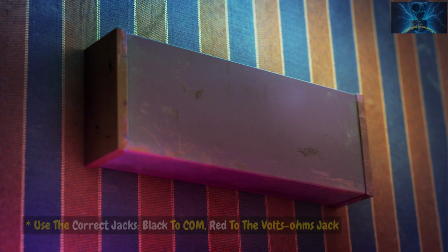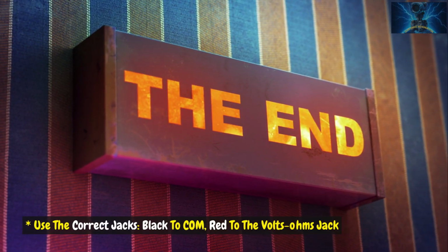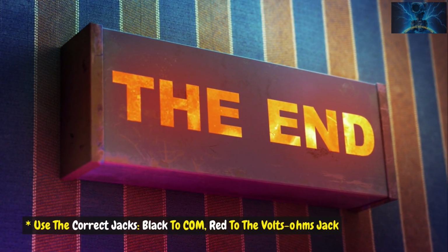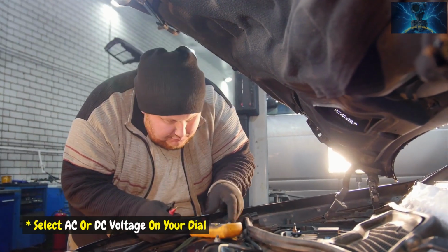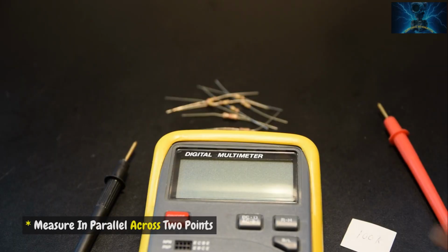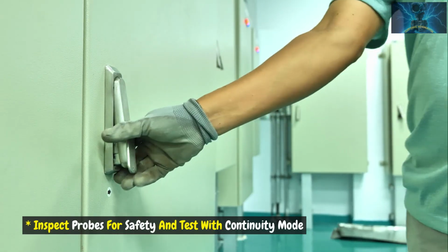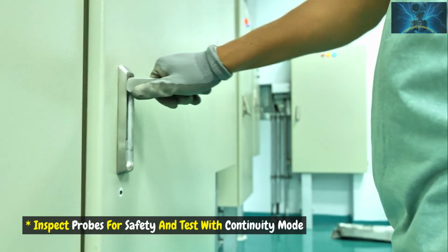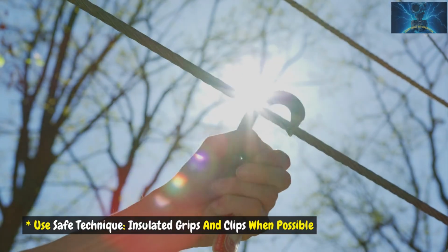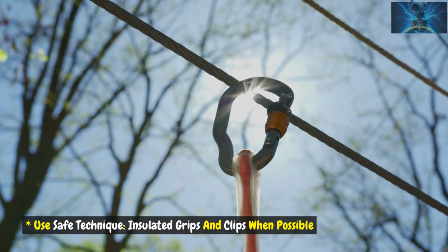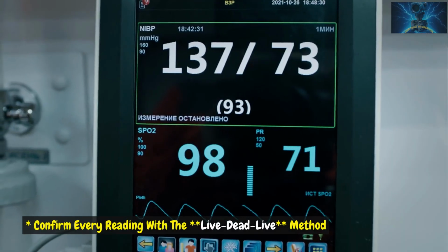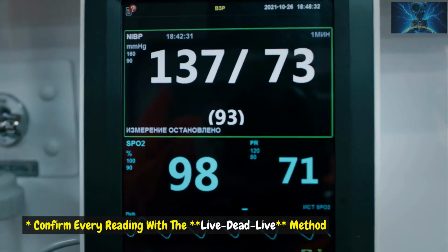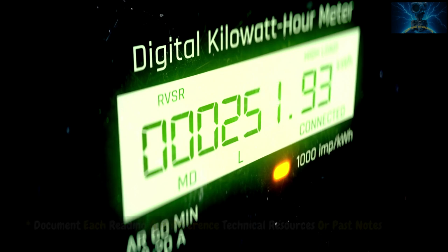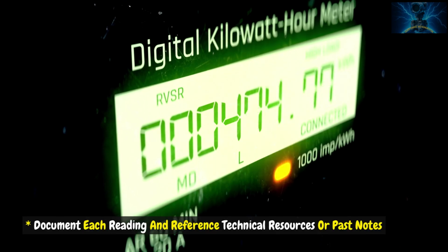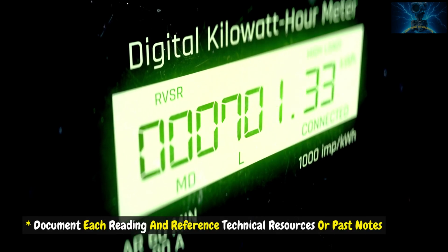Quick recap. Use the correct jacks. Black to COM, red to the volts-ohms jack. Select AC or DC voltage on your dial. Measure in parallel across 2 points. Inspect probes for safety and test with continuity mode. Use safe technique. Insulated grips and clips when possible. Confirm every reading with the live-dead-live method. Document each reading and reference technical resources or past notes.